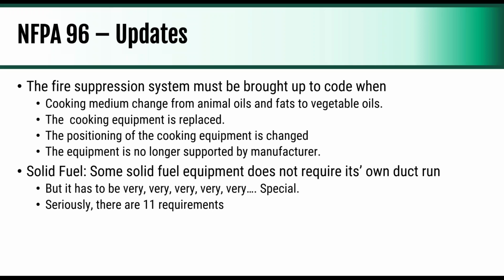When the position of the cooking equipment has changed, which is a no-brainer, if you have a fryer nozzle over a tilt skillet, it's not going to be effective in extinguishing the fire. And then if the equipment is no longer supported by the manufacturer. So that's end of life stuff. We don't see it a lot because most manufacturers of kitchen equipment do a decent part of their business in parts sales. And then lastly, solid fuel has always been, and most people understand that solid fuel appliances need their own duct run. NFPA 96 now actually allows for some solid fuel equipment not to require its own duct run.